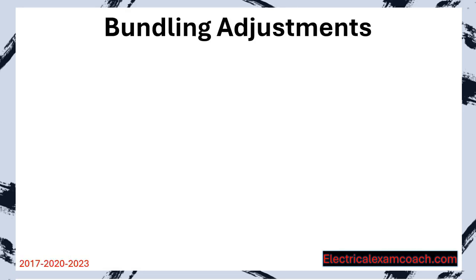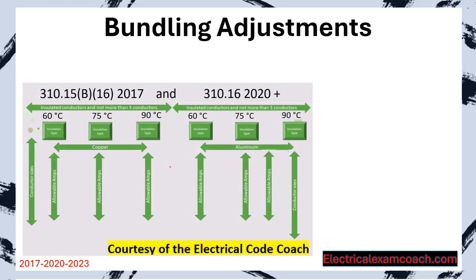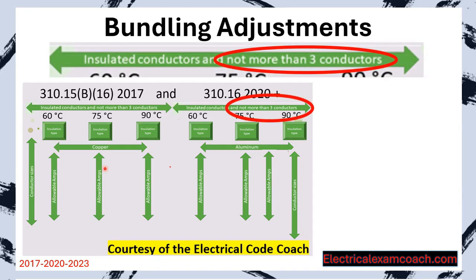Let's dive into bundling adjustments. Let's take a look at our primary ampacity table. These values in this table are true if — the question is if what? If you look at the paragraph above the table, the one that we said we would come back and look at later, it's got some parameters. It says these are the ampacities of these conductors if there are not more than three current carrying conductors inside of a cable, pipe, or even buried in the earth together.